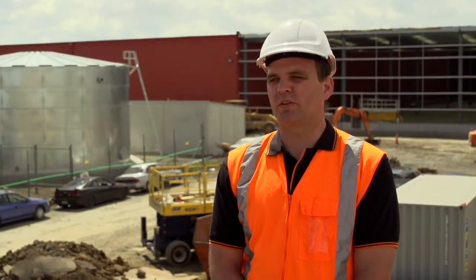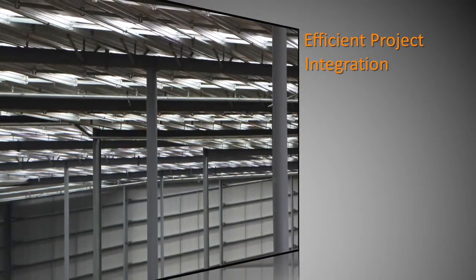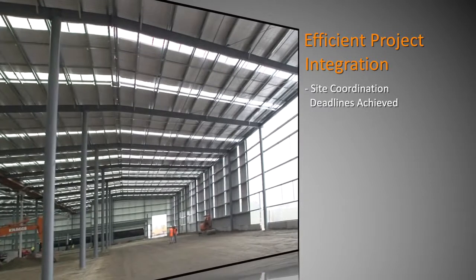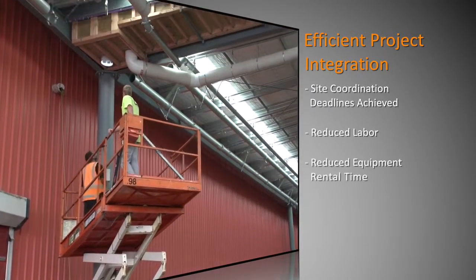Normally you'd build it once the roof and structure's in place in the air, but on this one we were given the opportunity to build the sprinkler pipework into roof sections on the ground with the structural steel guys, and then craned up into place in about 25 different segments. We had a limited window of two days to get the pipework installed on the ground — there was only one shot at getting it right, or we'd be installing in the air with additional access and labour to achieve the same result.